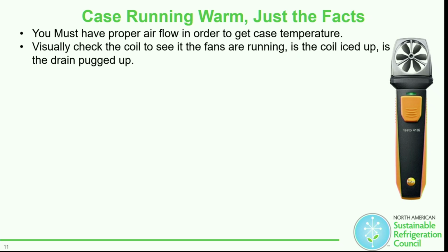Sometimes the other reason why we want to inspect the coil is to see what the frost pattern looks like. If you had a case that started going up in temperature because the frost pattern was only half the coil, there's a high probability that the superheat is high for some odd reason, even though the controller might be saying, hey, we're running good superheat. Well, if you didn't calibrate your sensors at first, that might be lying to you and give you a false operation of how the thing's actually supposed to run.